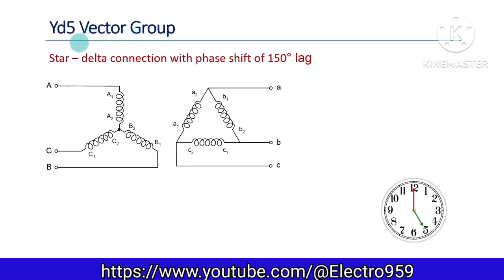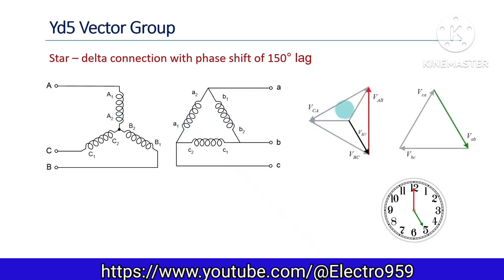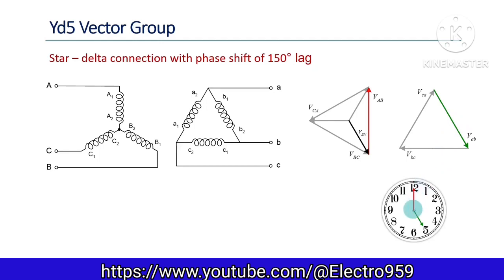Next we consider the YD5 vector group. The primary is star connected and the secondary is delta connected. In the phasor diagram, line voltages on the star-connected primary side are decomposed into corresponding phase voltages. Taking line voltage VAB as the primary side reference, we need to take VAB for the secondary side also. Here VAB comes from winding B of the secondary, and the voltage induced in it will be in phase with the phase voltage of winding B on the primary. The secondary line voltage is lagging by 150 degrees from the corresponding primary voltage — represented by the 5 o'clock hand position. The simplified connection diagram and displacement diagram are shown.